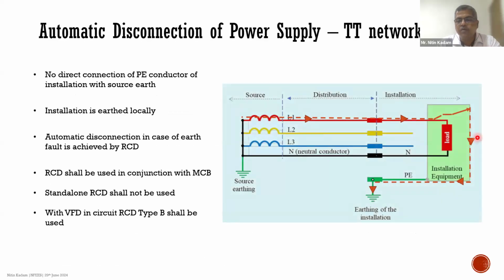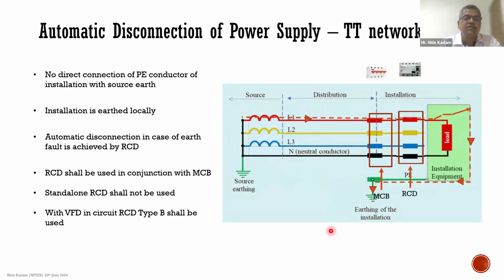In case of a TT network, as we had seen earlier, there is no direct connection between the source earthing and the earthing which is done at the installation. But according to the code requirements and the protection that is required, the MCB is a must. In addition to that, an RCD is a must in the TT network, because the fault loop impedance is not going to be low enough for the MCB to trip, there would be leakages happening, and these leakages will be detected by the RCD and the RCD will trip.